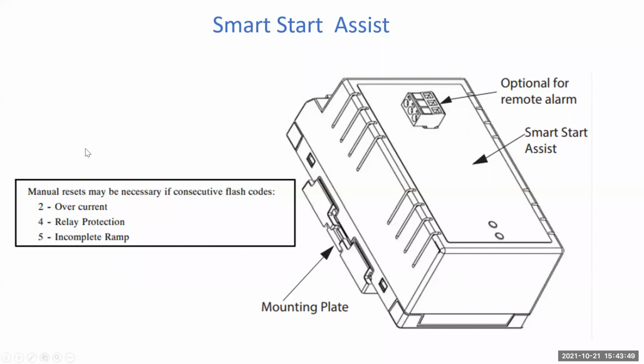Now we're going to get into the Smart Start Assist. This is on the GT series. Smart Start Assist is designed to reduce the inrush current during single phase scroll startup. The kit contains two parts, the main part and the mounting plate. The kit is installed on top of the unit's electrical box.